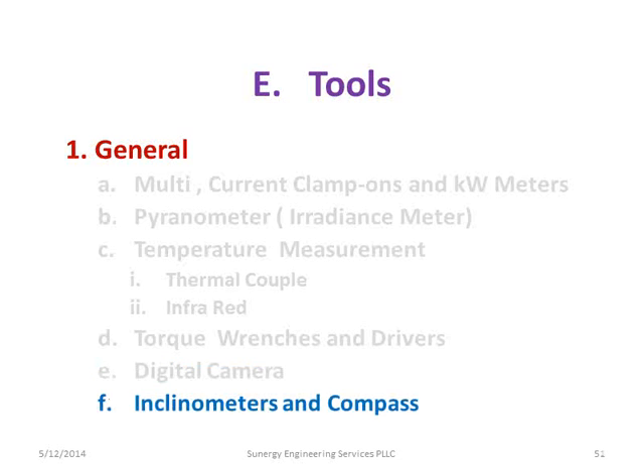In some cases, you might need an inclinometer or a compass to verify the orientation of the roof and what the angle of the roof is. In some places, they actually require you to do like a Pathfinder or a SunEye, where you document exactly what the shading issue is on that roof. And in some places, they won't even give you incentive payments unless there's a minimum amount of shading. That's not something we have to worry about that much here, but it is something good to document. Because if you have a different performance than what you expect on a certain site, that might be one of the reasons why you have a lower performance. The other site might have a better orientation.